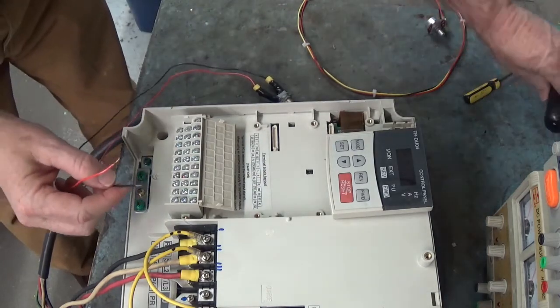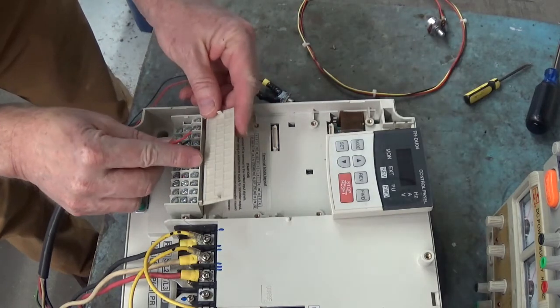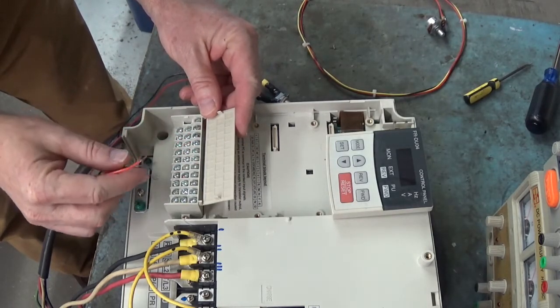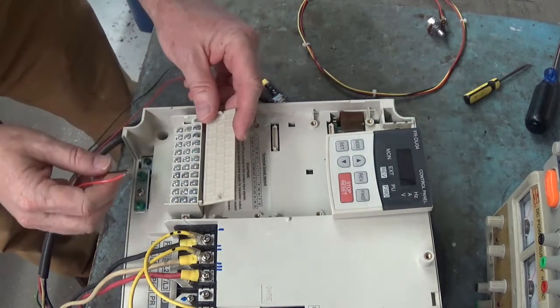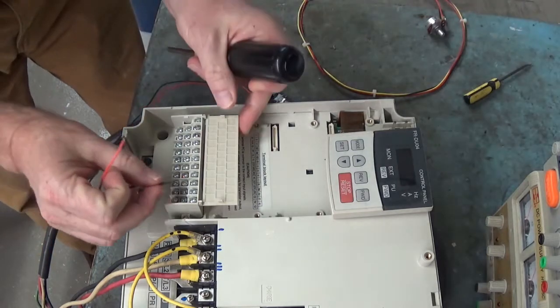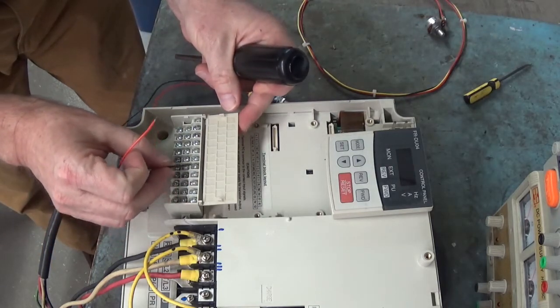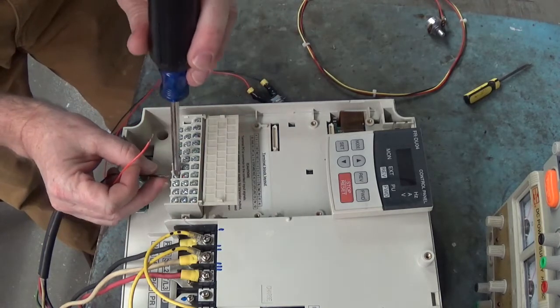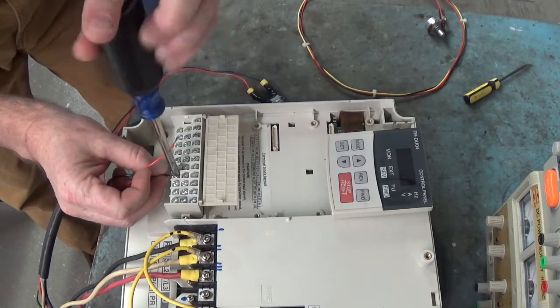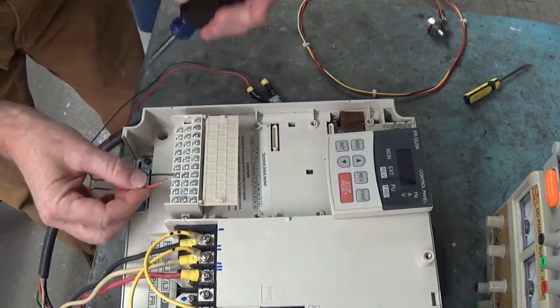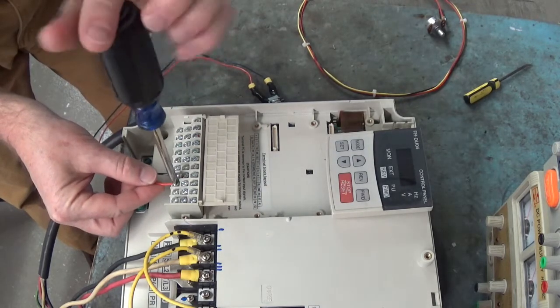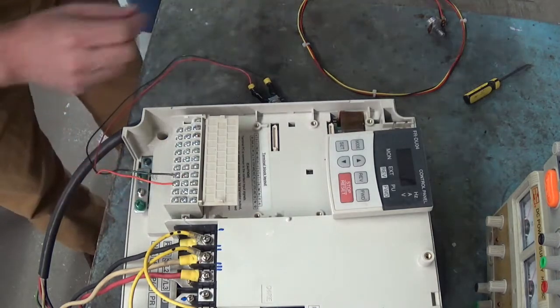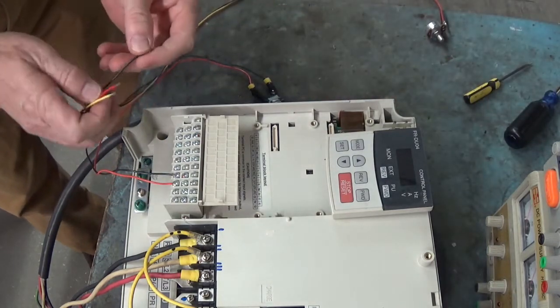We're going to hook our switch to the SD terminal and the STF terminal. The STF is start forward. That's one, two, three, four, five back on the bottom row. STF is right beside it. Start forward. I'll put the diagrams for these connections at the end of the video.